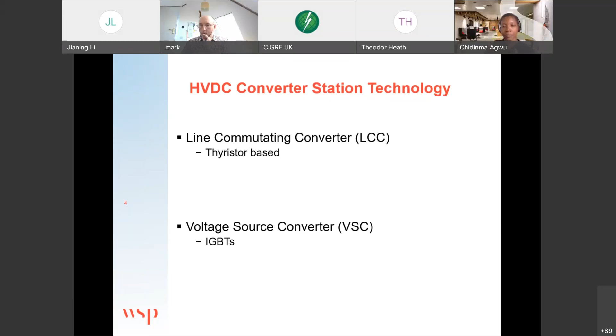Depending on the project location, LCCs and VSCs are still required, although I know in Europe it's VSCs that are the more common technology or converter station that you'll hear being spoken about. But LCC is a lot more mature, and as mentioned by Theodor, has a higher power capability. So for example, it's used more in countries such as China, India, Brazil, where you want to transfer a lot more power, while VSC converters are used, for example, a bit more in Europe, where you want your converter station and your link to be able to support the AC network. So those are the technologies that basically drive the converters.